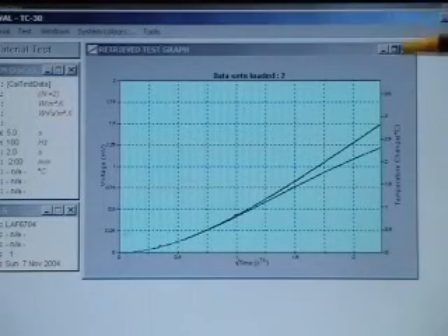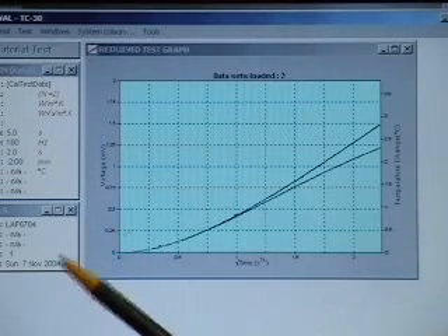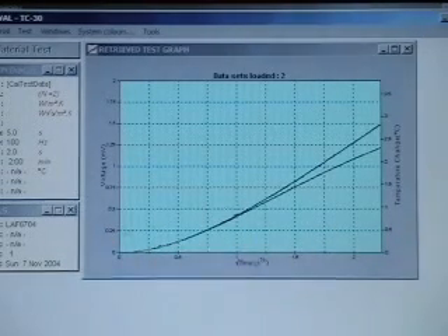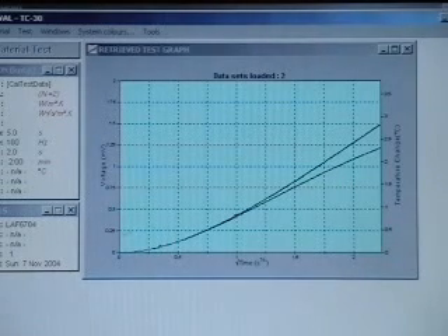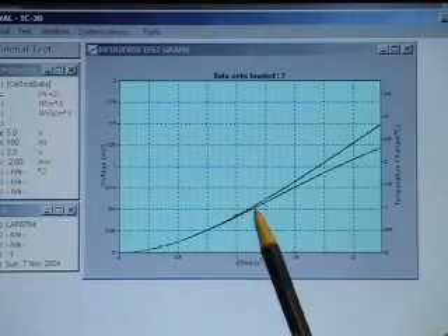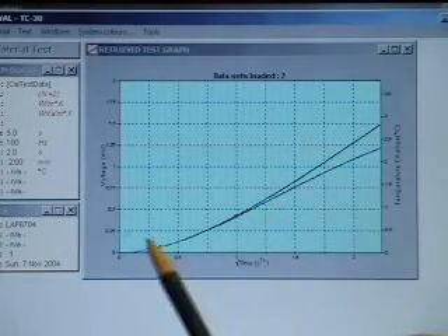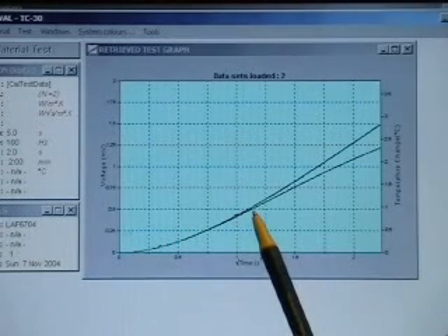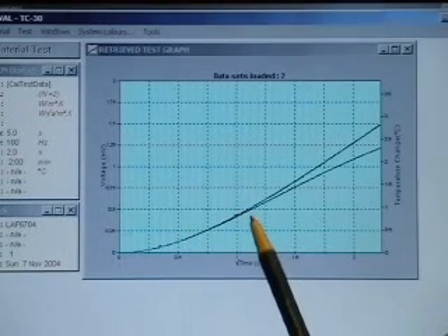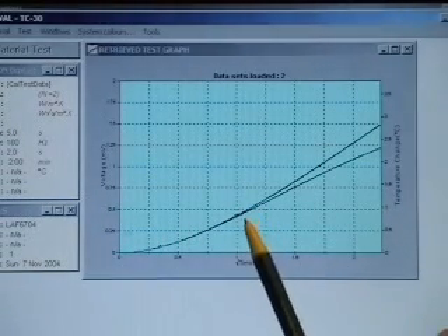Let's take a look at the data. This graph represents the temperature rise versus the square root of time on the raw data that we just performed. I've saved those 2 data files and overlaid them on top of each other. As you can see, there's a very consistent portion of this line. This is where the heat is penetrated through the 5 layers of paper and deviated into the conductive or the insulative backing material. In this case, this gives us the total allowable test time for our 5 layers of paper, approximately 1 second.